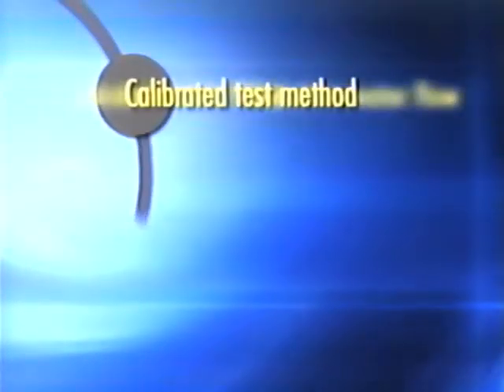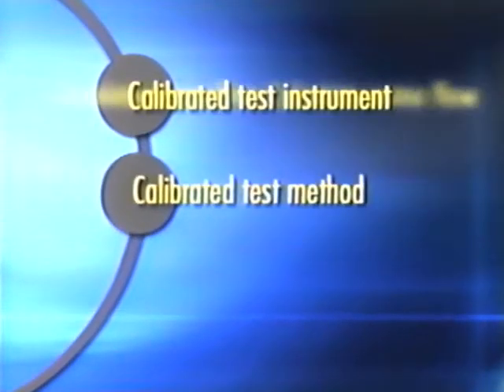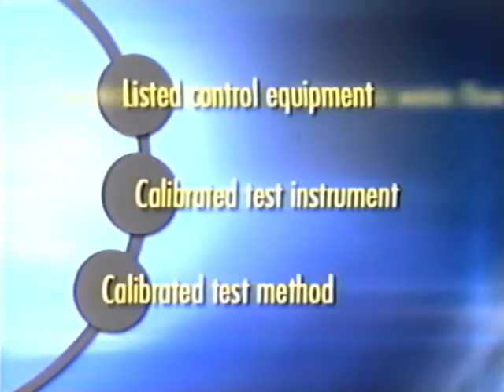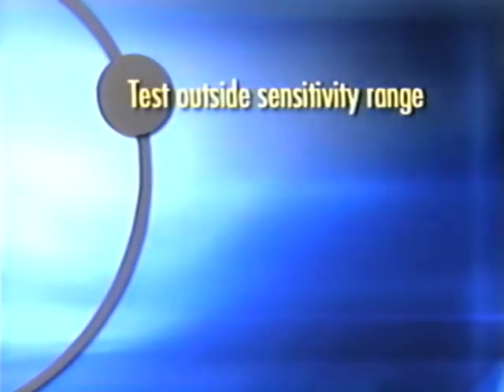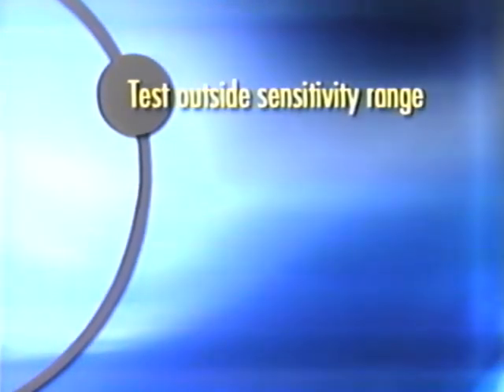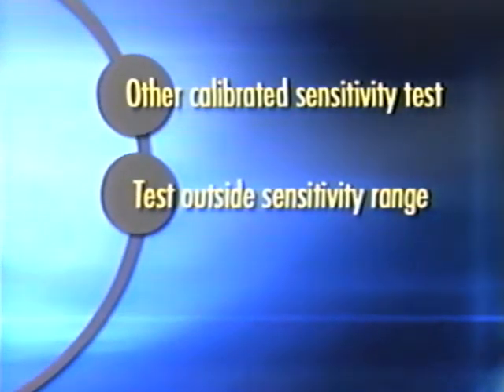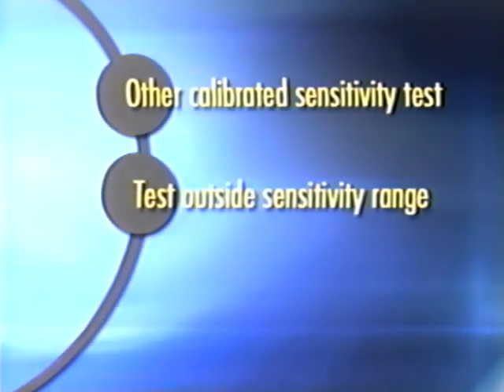You may perform a sensitivity test in one of several ways: by a calibrated test method, a manufacturer's calibrated sensitivity test instrument, listed control equipment arranged for the purpose, a setup with the control unit where the detector causes a signal when it is outside its listed sensitivity range, or another calibrated sensitivity test approved by the authority having jurisdiction.